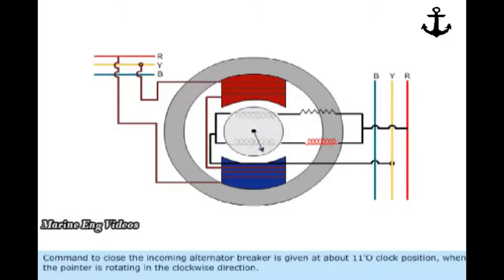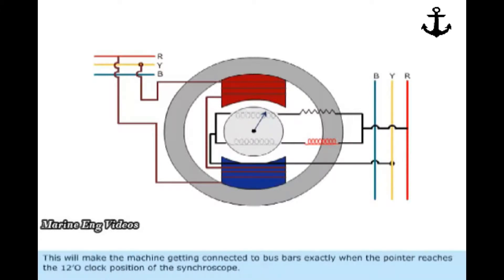Command to close the incoming alternator breaker is given at about 11 o'clock position when the pointer is rotating in the clockwise direction. This will make the machine getting connected to busbars exactly when the pointer reaches the 12 o'clock position of the synchroscope.